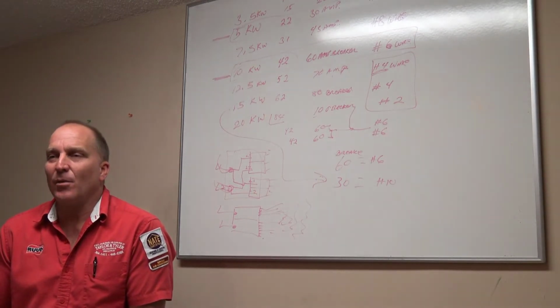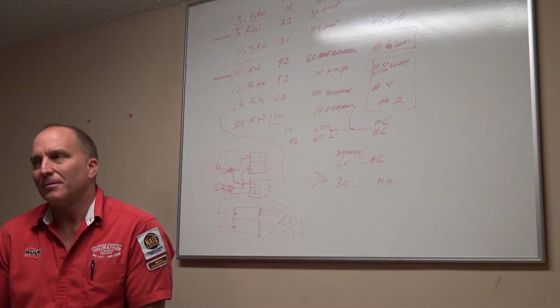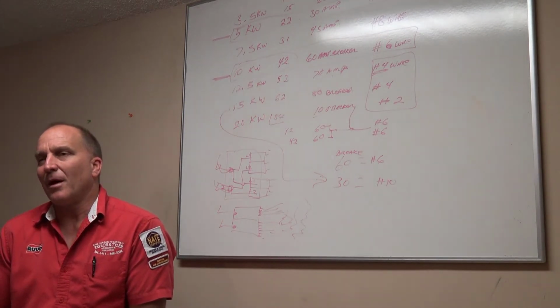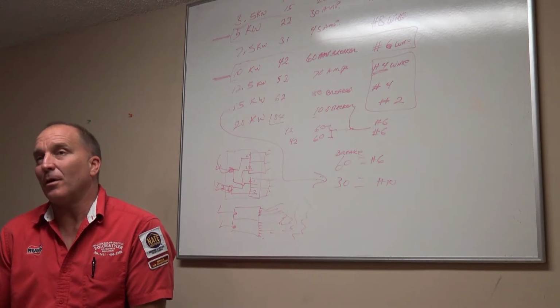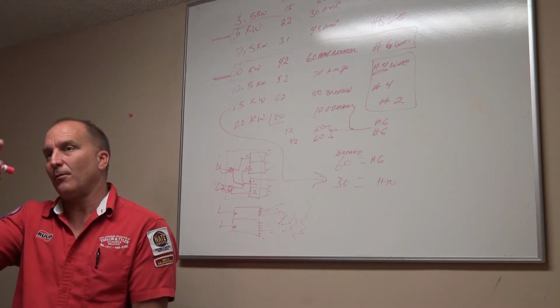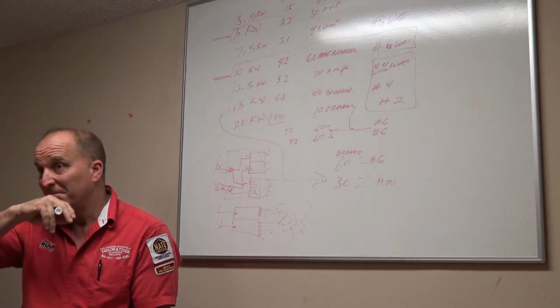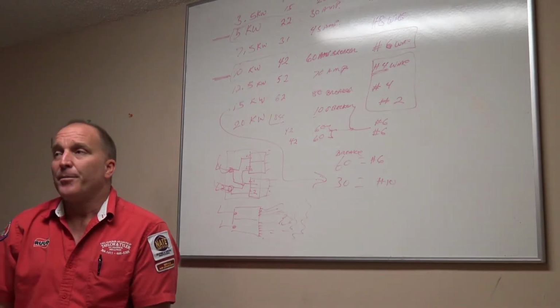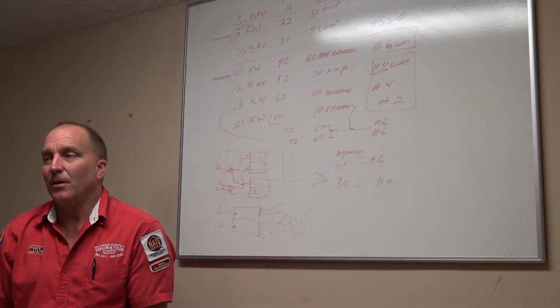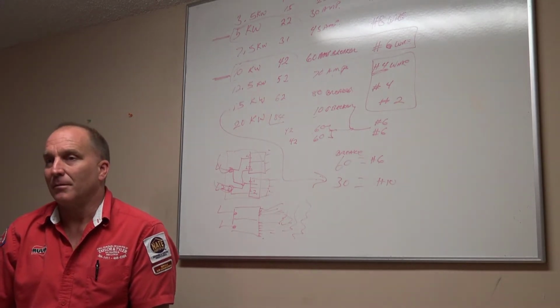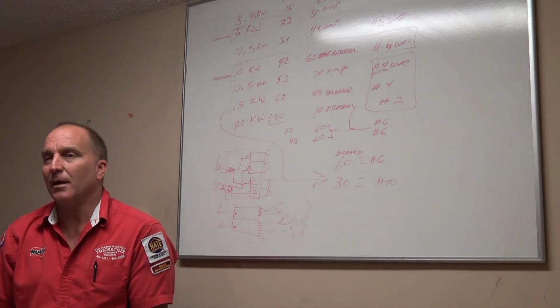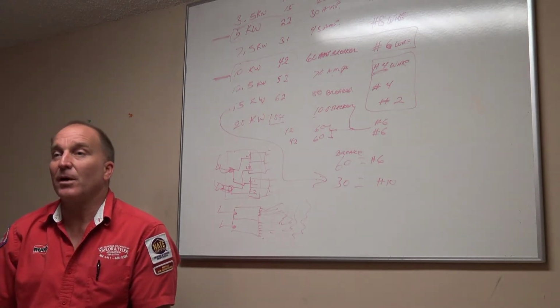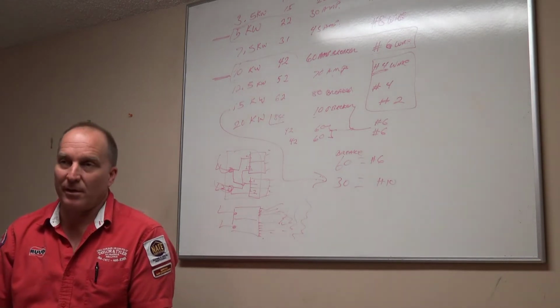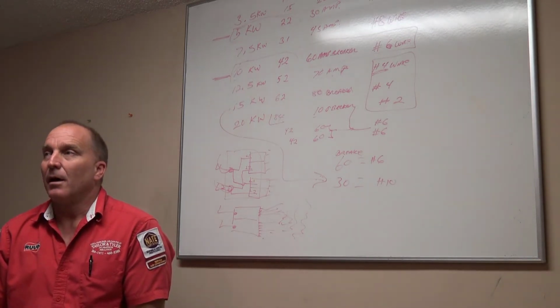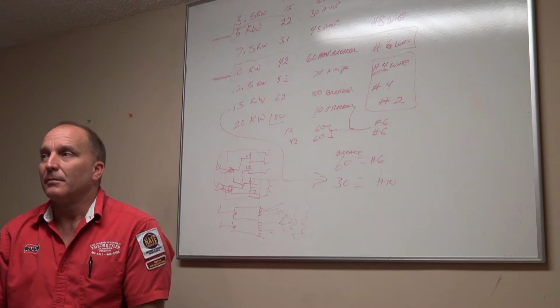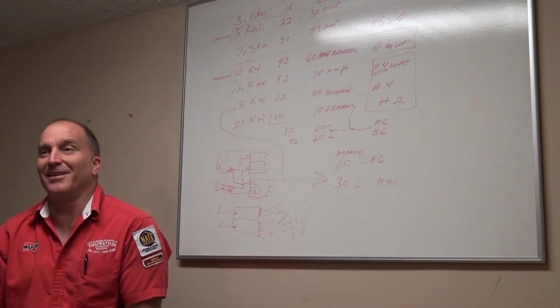Your L1 is going to be what? Your power going into your circuit board. Then there's going to be L1 next to it, which will be the power coming from your switch to your board, and then from your board to your transformer. That's all high voltage. Where does your neutral wire go? Your white wire coming from your switch. L2? No, it's a circuit board. It's a gas heat system in this case, so there is no L2, it's the neutral. So it's going to go to your neutral on your board in this particular case. Okay? I don't think there are any more wires left, guys.